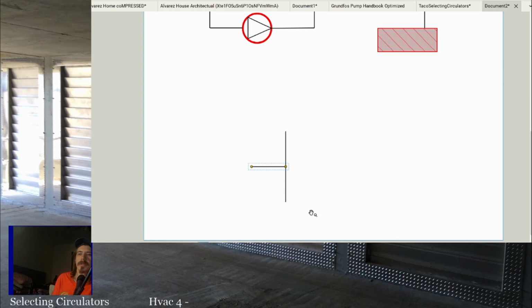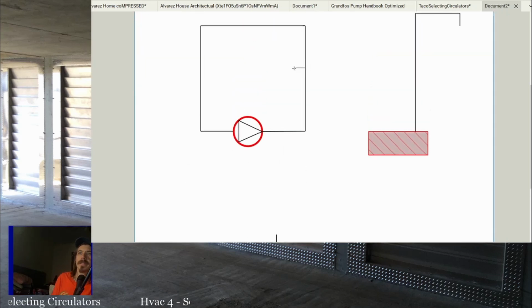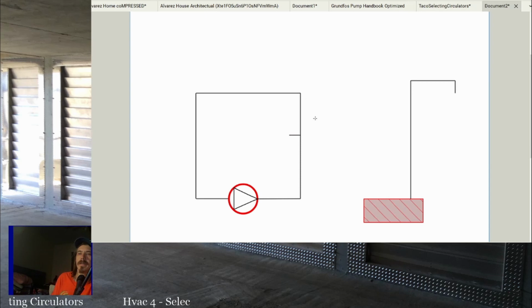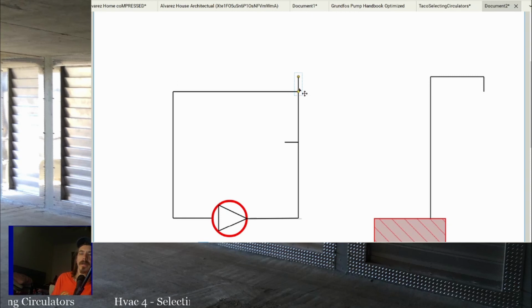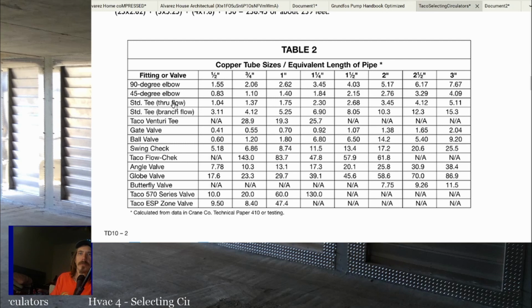There's your run, there's your branch. If the run is continuing the loop back to the boiler, right? So if you've got a T here going to a radiator, and the flow just continues around the path, that is a straight run T. A branch T would be if you need to continue the loop this way, but you're catching a radiator that way or something. In other words, the water's going to favor continuing up through whatever appliance you have that way instead of maintaining in the loop. So that's what they're talking about there, through flow versus branch flow.